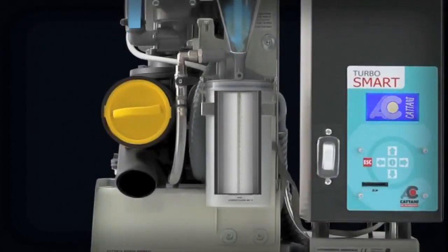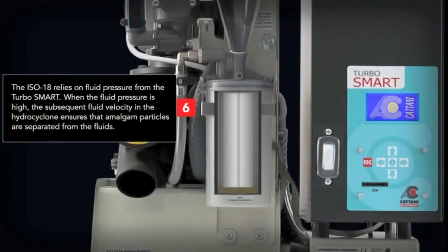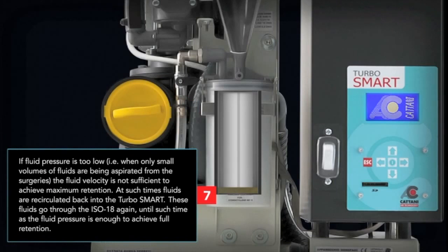The ISO 18 amalgam separator relies on fluid pressure from the TurboSmart. When the fluid pressure is high, the subsequent fluid velocity in the hydrocyclone ensures the amalgam particles are separated from the fluids. If fluid pressure is too low, for example when only small volumes of fluids are being aspirated from the surgeries, the fluid velocity will not be sufficient to achieve a maximum separation of particles. At such times, fluids are recirculated back into the TurboSmart. These fluids go through the ISO 18 amalgam separator again until such time as the fluid pressure is enough to achieve full separation.